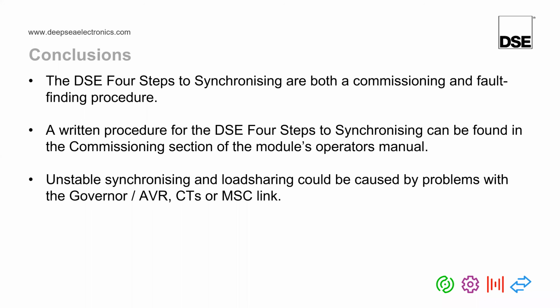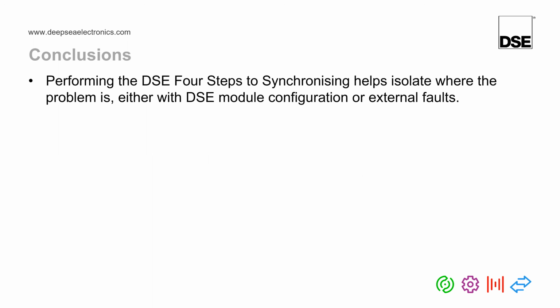Any unstable synchronizing or load sharing issues could be caused by problems with your governor, AVR, current transformers, or MSC link. By doing the 4 steps, you will actually isolate where these issues are lying. In addition to isolating where these issues lie, potentially with the wiring or configuration with the DeepSea module, the 4 steps will also help you identify any potential external faults as well.